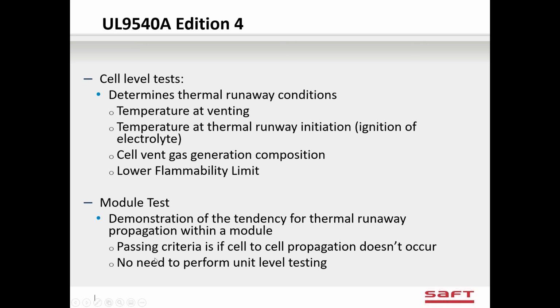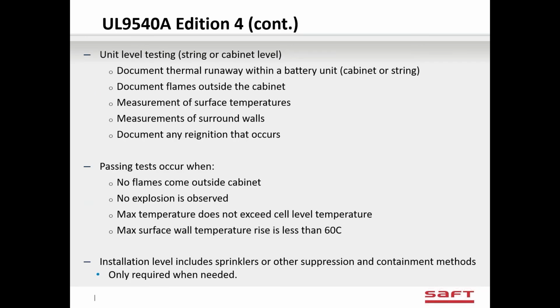But in all lithium-ion cells, the gas in the electrolyte is flammable. So I don't know of any lithium-ion battery that can stop at the module test. This 9540A can be done for other chemistries, sodium nickel or some other chemistries that might not have flammable gas, but lithium-ion batteries are always going to move on to the unit level testing at least.